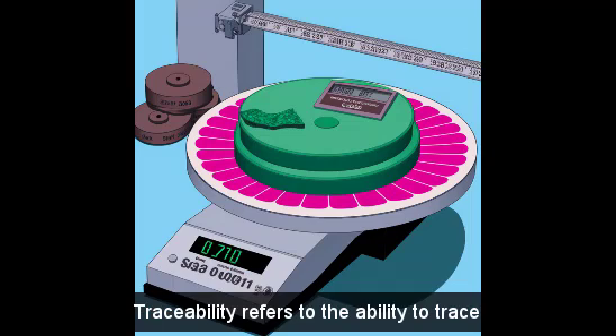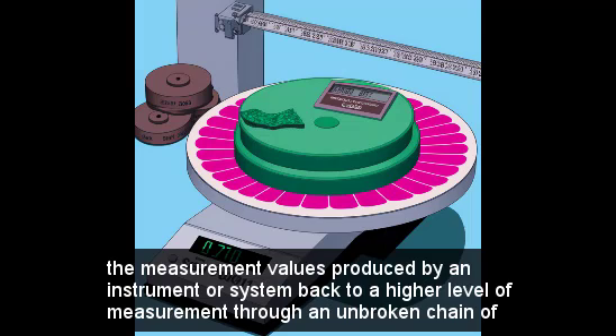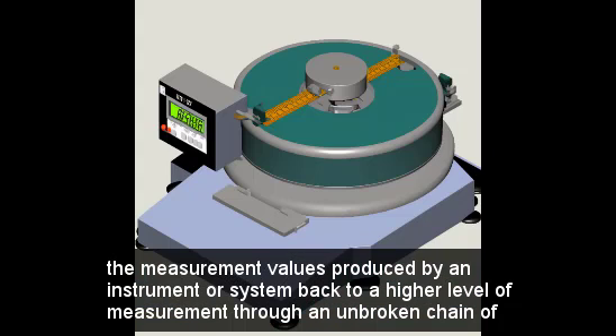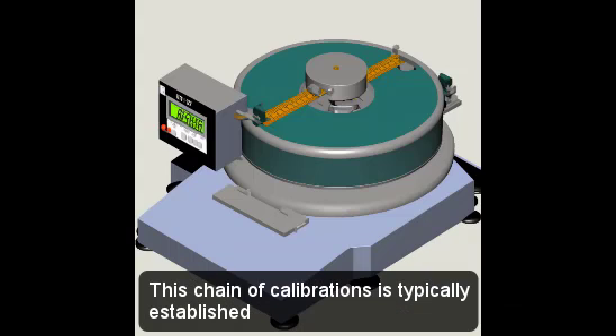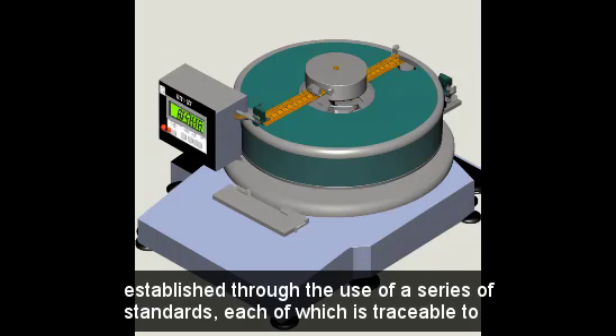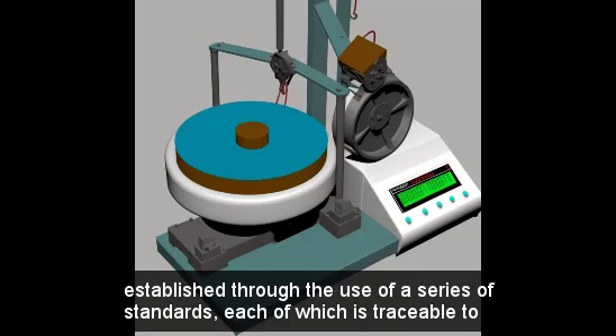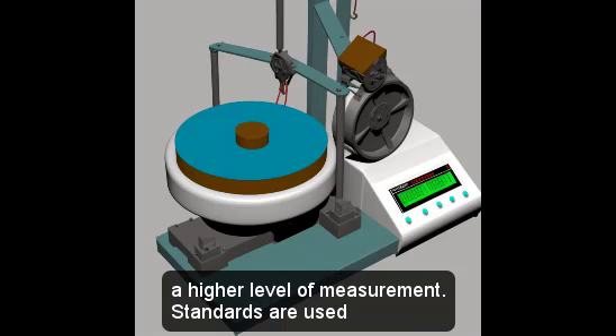Traceability refers to the ability to trace the measurement values produced by an instrument or system back to a higher level of measurement through an unbroken chain of calibrations. This chain of calibrations is typically established through the use of a series of standards, each of which is traceable to a higher level of measurement.